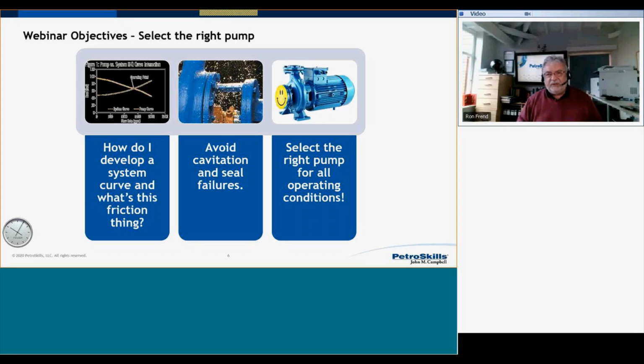So we're going to develop a system curve, and we're going to use that to help us choose the right pump. That's also going to have some other implications, and we're going to talk about the implications if we choose the wrong pump, that we might get problems with cavitation, you might get problems with seal failures, and we'll see why that happens. And at the end of it, what we want is a pump that's going to be correct, it's going to be applicable, it's going to be useful for all of those operating conditions. So that's our objectives. So let's start.